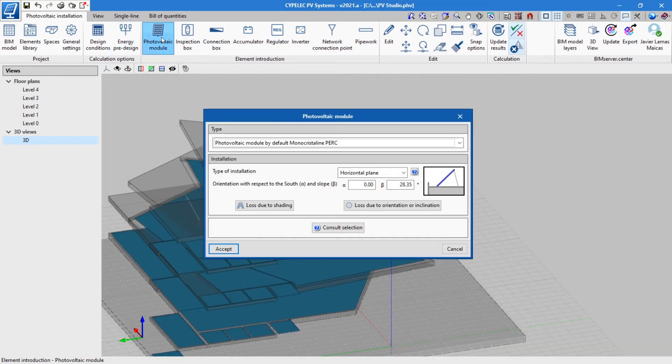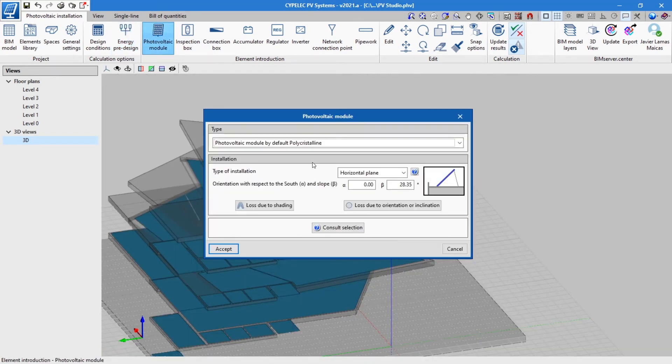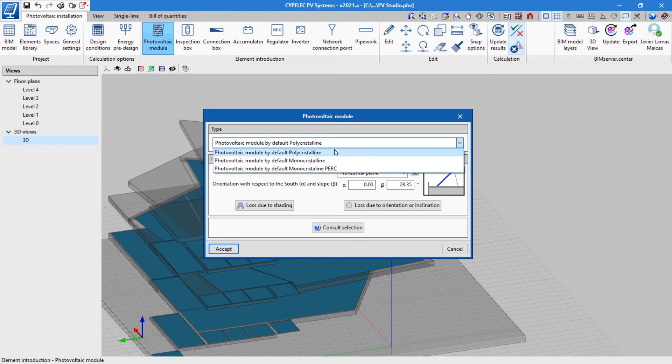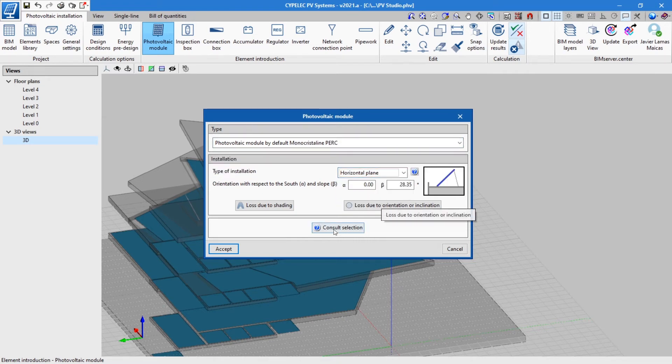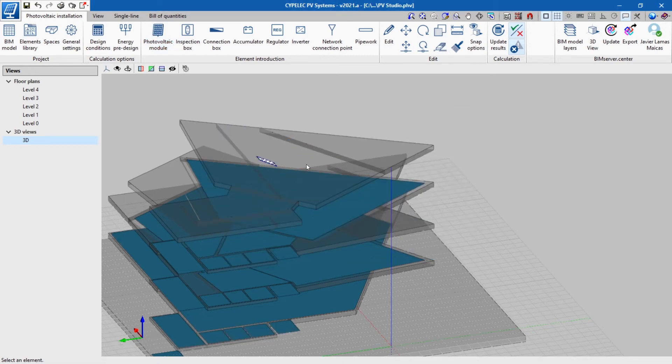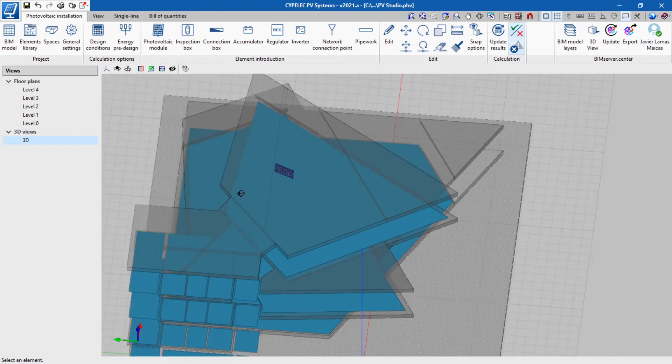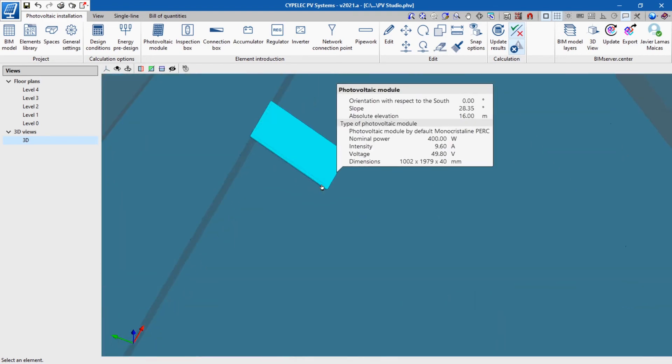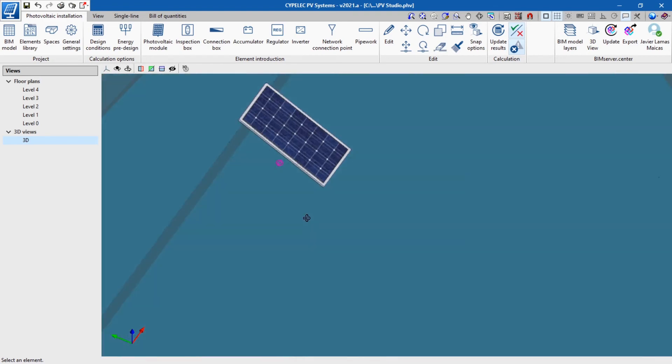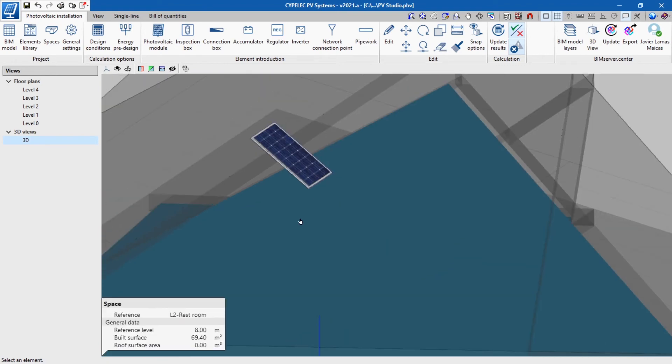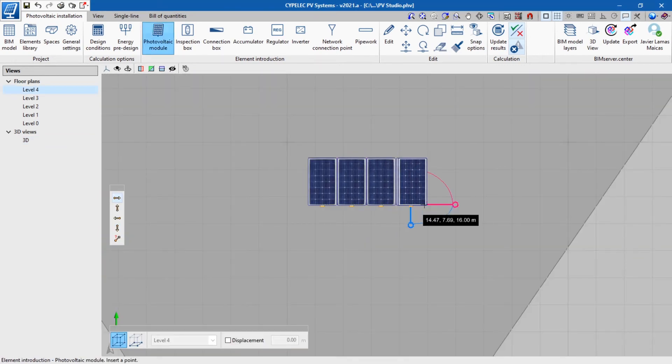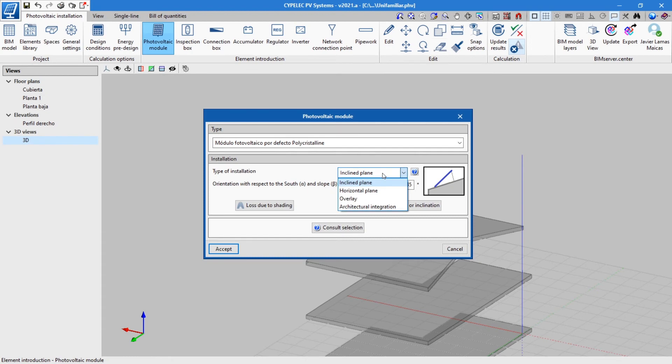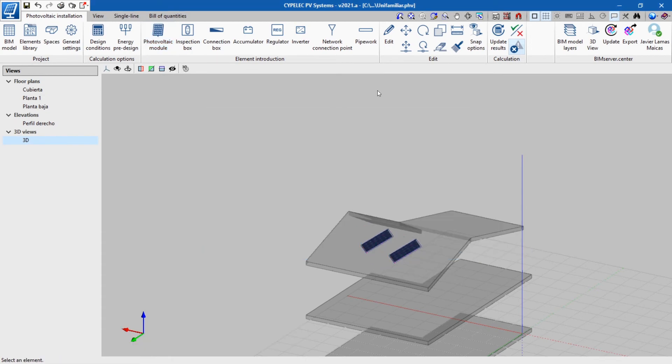We will continue with modeling the installation. First, we will select the type of solar panel in addition to the type of installation, the orientation, and the slope. When selecting the horizontal plane installation type and inputting an inclination, the application allows it to be easily inserted into the 3D model. If the overlay option is selected, clicking on update results after placing the photovoltaic module enables the program to detect the roof plane and align the module with the roof slope.